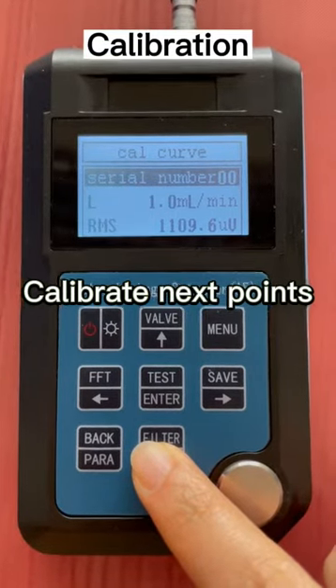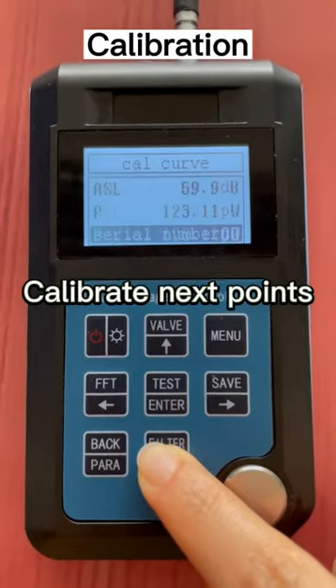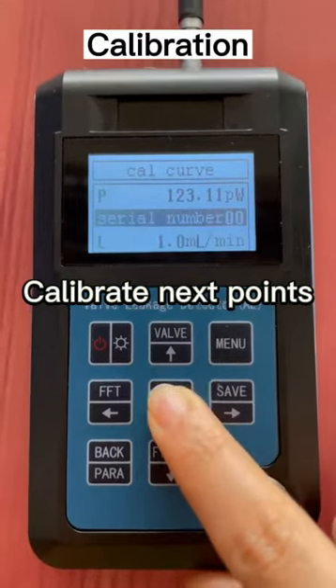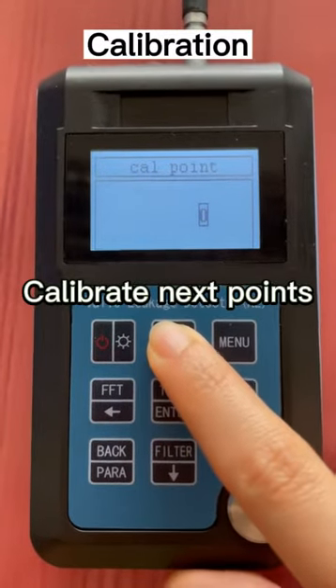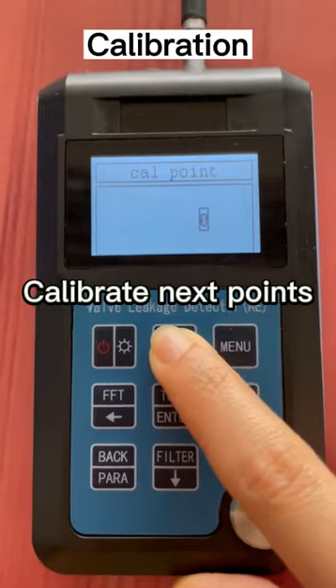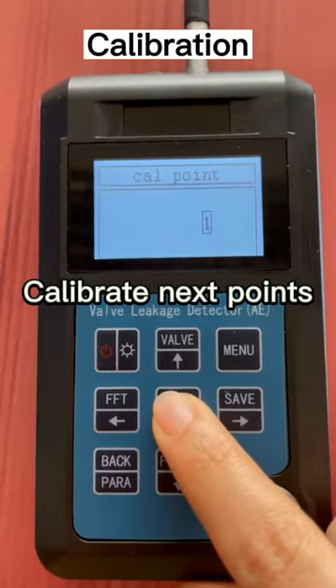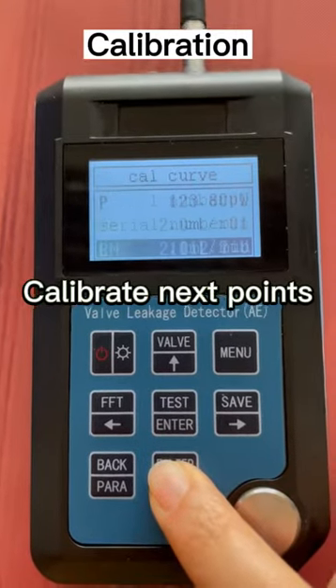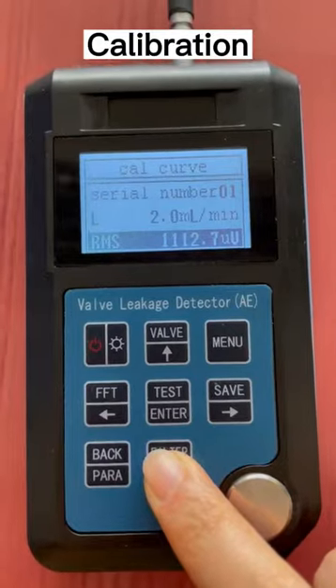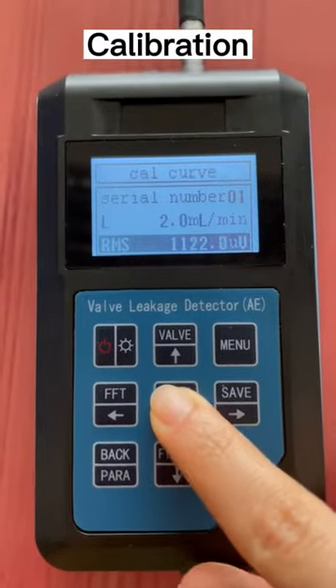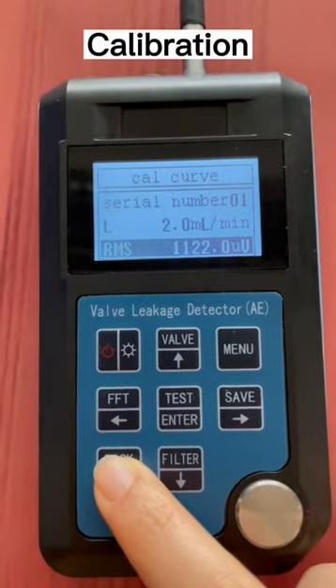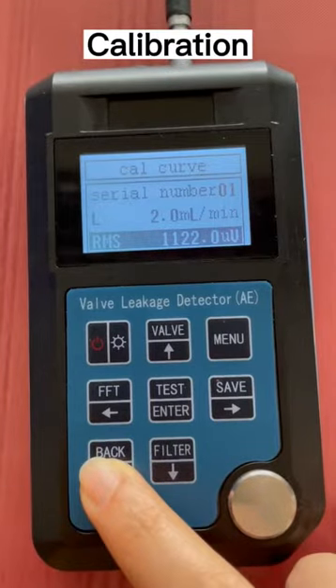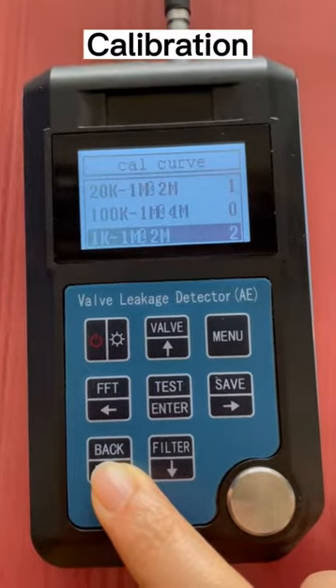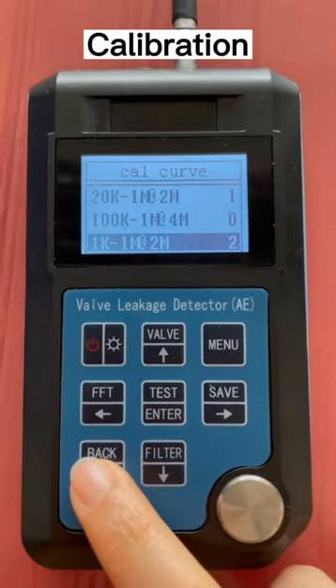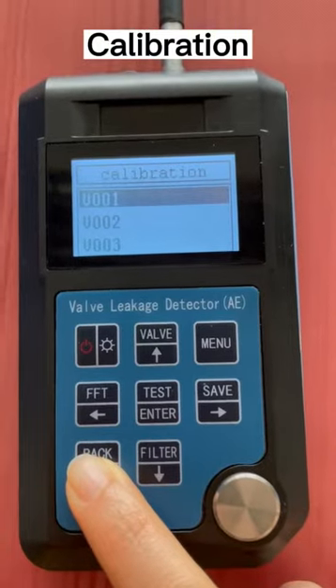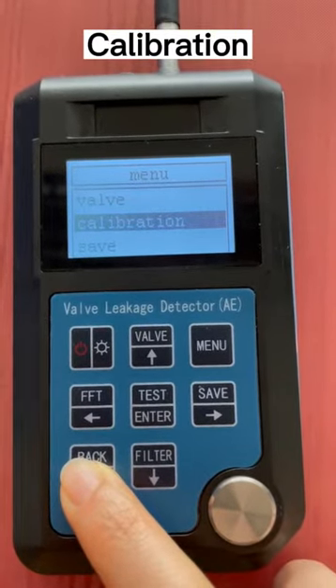After the first calibration point is done, move the cursor back to the serial number. Press Enter and increase the number by 1 by pressing the up arrow key. Press Confirm, and now it is at the second calibration curve point. Repeat the steps we mentioned before and get more calibration points. Press the back key when you finish calibration point curve testing. Press the back key to exit the calibration page. It is now ready to measure the valve leakage.